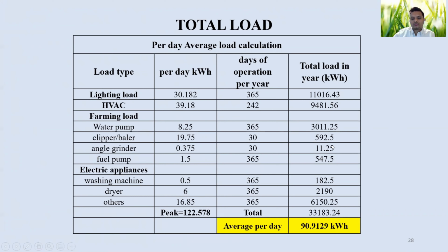So in this way, we calculated the total amount of energy that we're going to need over 1 year, which came to be 33,183.24 kilowatt hour. So this is the total amount of energy that we're going to need over a 1 year period. When we calculated that energy on average per day, it came to be 90.91 kilowatt hour. So our peak energy in a day is 122.578 kilowatt hour, and the average energy per day is 90.91 kilowatt hour. So this is our load calculation.